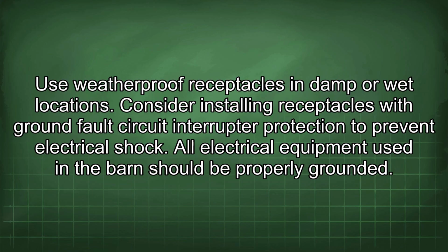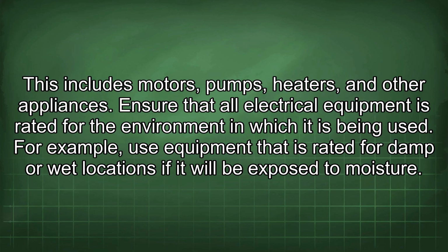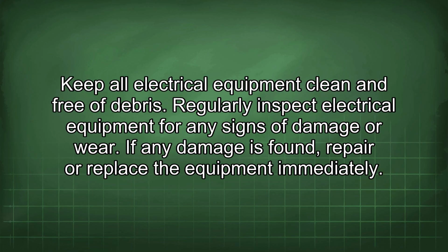All electrical equipment used in the barn should be properly grounded. This includes motors, pumps, heaters, and other appliances. Ensure that all electrical equipment is rated for the environment in which it is being used. For example, use equipment that is rated for damp or wet locations if it will be exposed to moisture. Keep all electrical equipment clean and free of debris. Regularly inspect electrical equipment for any signs of damage or wear. If any damage is found, repair or replace the equipment immediately.